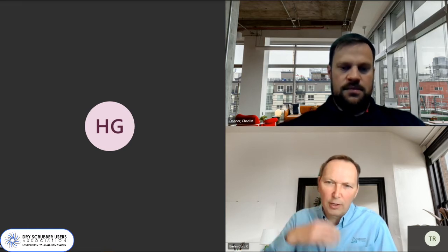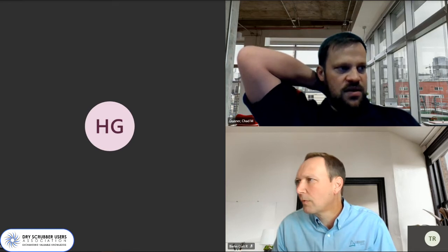Okay, thanks. And on your silos, what level transmitters have you found to be most reliable? Because during unloading you're dealing with a very loose bulk density, and then when it's in operation, it's probably more of a packed operation. So we use a Siemens radar level transmitter that has an air purge on the lens to keep any dusting off of it, and we see very good trending with it over time. You will see directly after you unload a truck a kind of high point, but then it settles down within minutes and falls right in line with where the trend would have been. If anybody wants or needs any information on those, I can send that out.